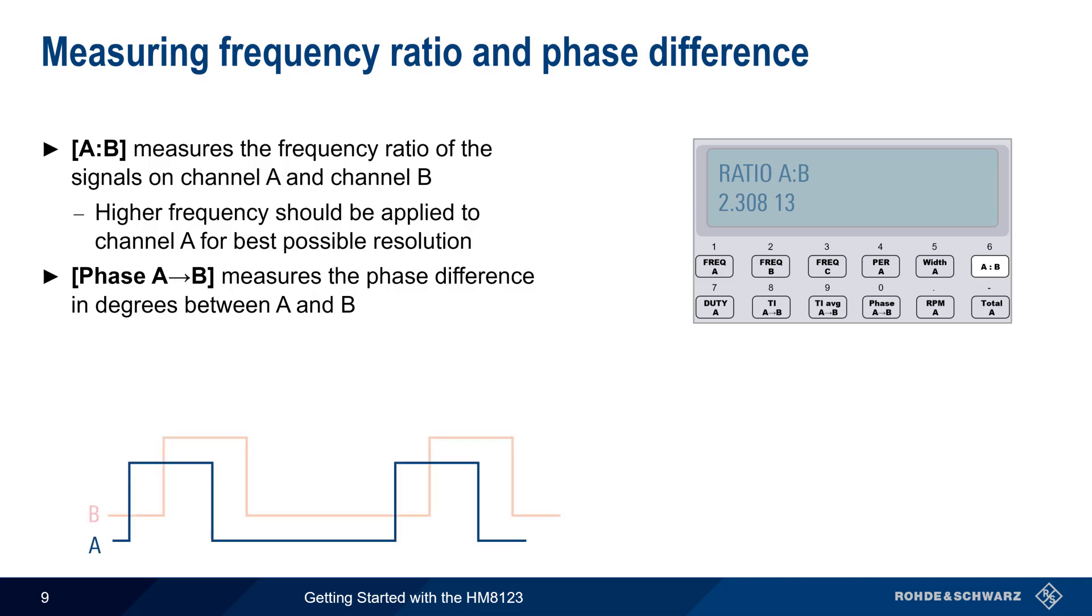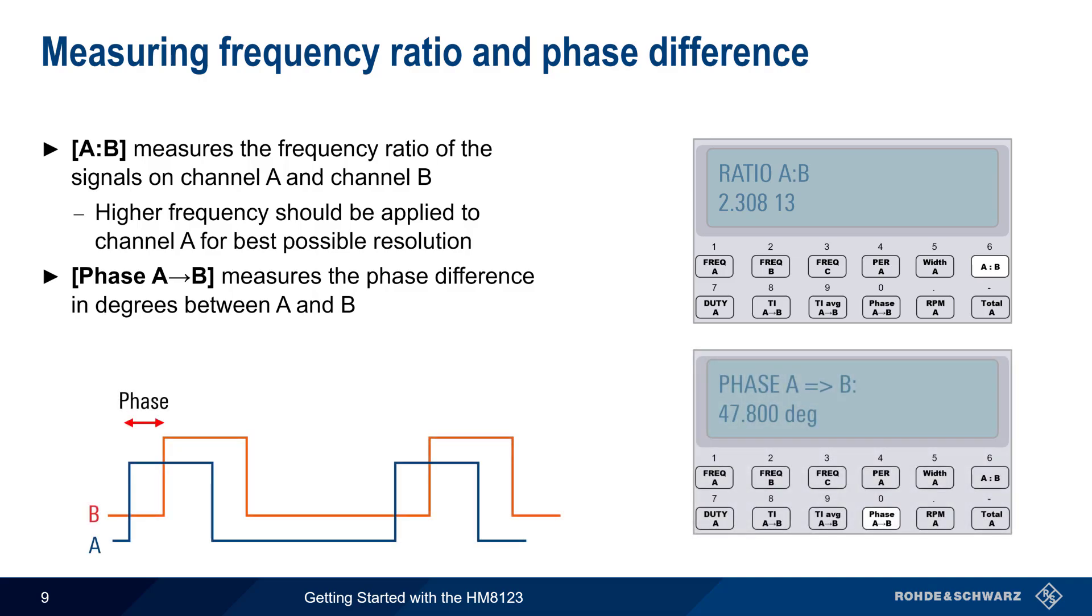Next we'll look at the frequency ratio between inputs A and B, which is enabled using the AB key. Note that the best accuracy is obtained if the higher frequency is applied to channel A. The phase AB button measures the phase difference in degrees between the A and B inputs. Unlike frequency ratio, this phase difference measurement is only possible on square wave signals.